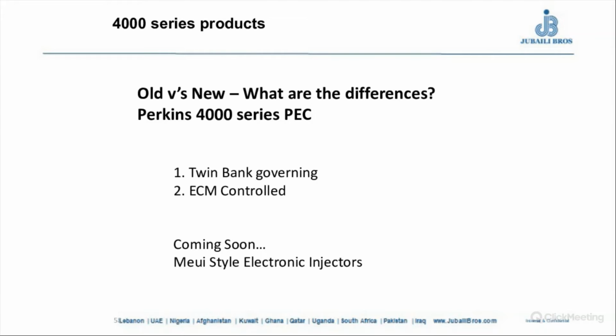Each actuator is connected to a bank, one for bank A, one for bank B. Why? Because whenever a low load is applied on the engine, if both banks are working, the engine will start to consume oil. Whenever you have low loads applied on any engine in general, the piston rings will not open up properly and will not work as a perfect seal, so you will be having oil consumption.